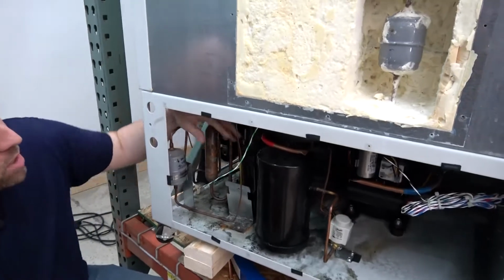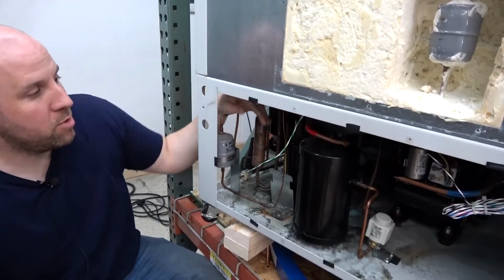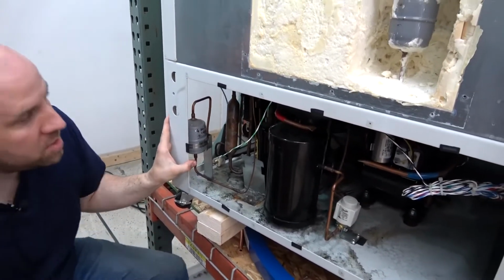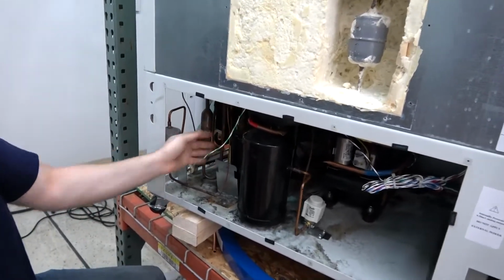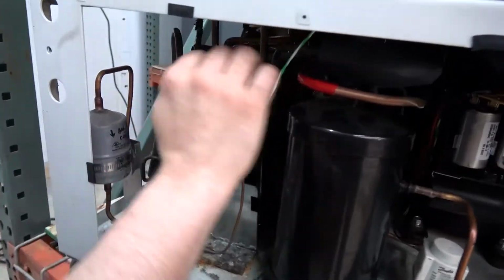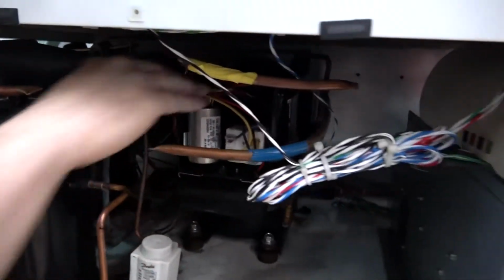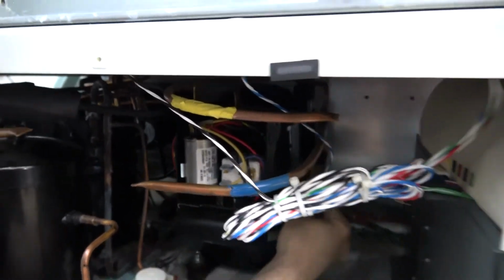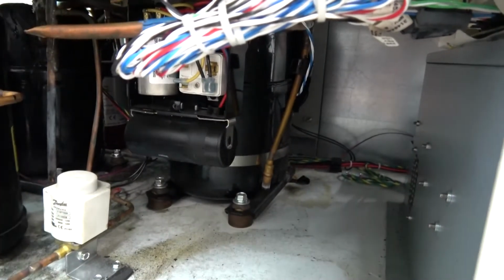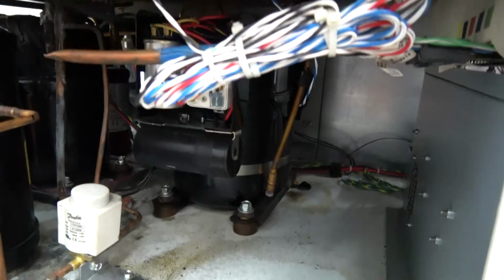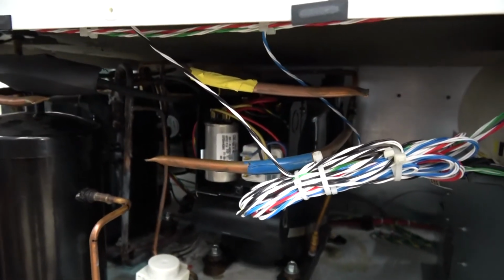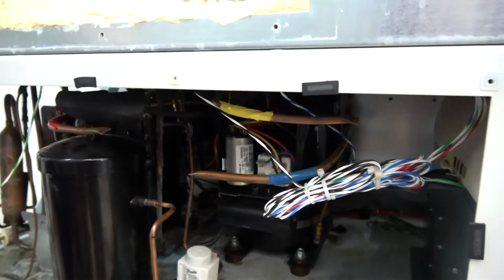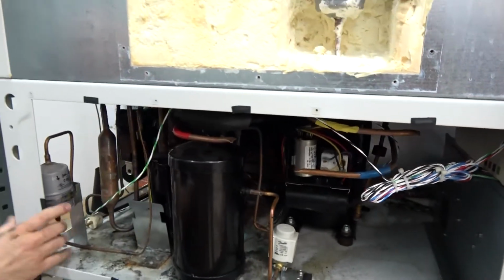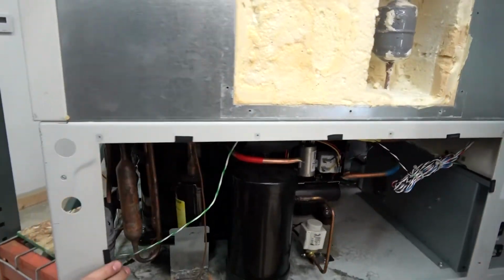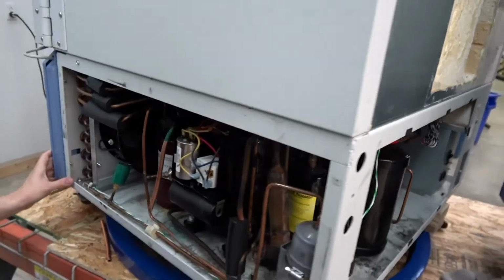So it's really important to have these devices in these systems because it prevents liquid from getting back to the compressor on the suction side. So it comes through here, the liquid stays, the gas passes through and goes back into the compressor. So this is where the gas comes out and the gas comes in back here after it's all done. And then the liquid sits in here, and once it evaporates, it carries on back into the return line. That's the first stage. On the second stage, it's much the same with a few differences.